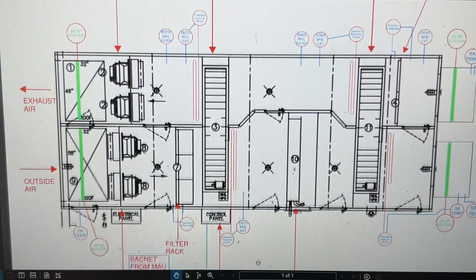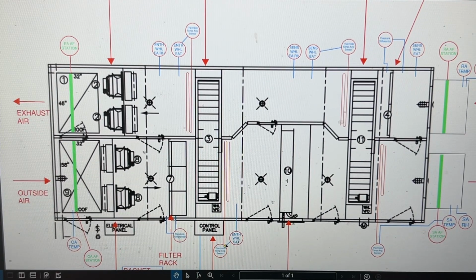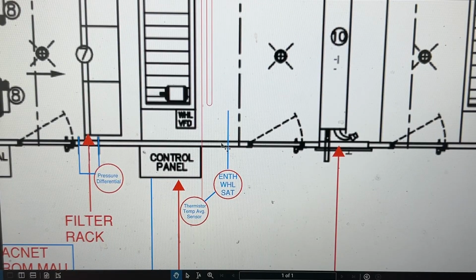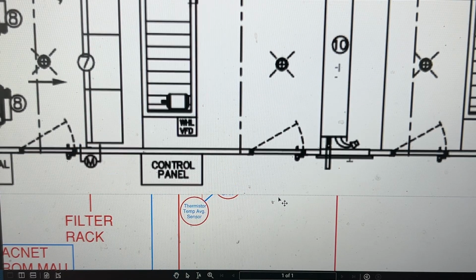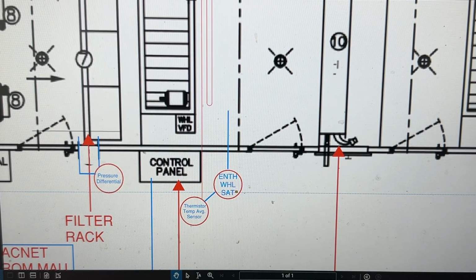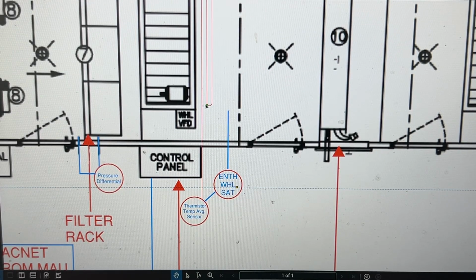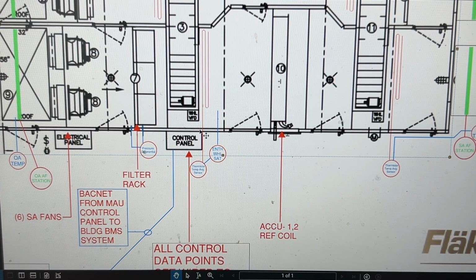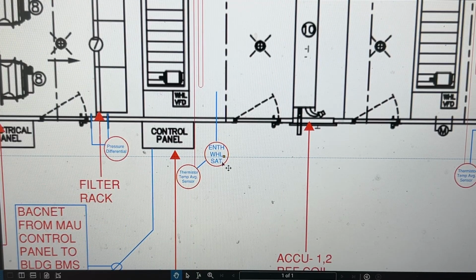Then they pass through our enthalpy wheel. Now on the discharge side of the enthalpy wheel, there is a thermistor, which, as shown here, is a small copper tubing that gets wound across the wheel as an averaging sensor, so that it's uniform throughout the whole airstream, not just picking up top, bottom, or the middle. We wind that kind of like Christmas lights on the discharge side of that wheel to get an accurate temperature. Then we have a control point for the enthalpy wheel supply air temperature, which pulls from that averaging sensor.